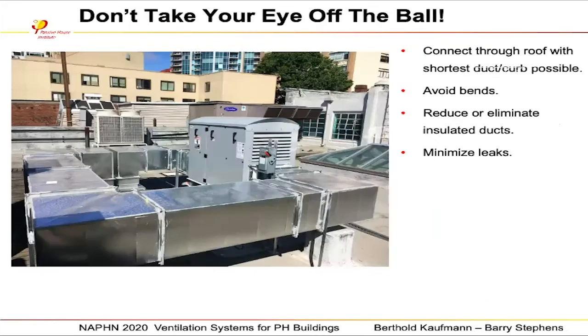One other thing with ductwork is beware the change order or the out of control contractor. What you can see here, the entry point for these two ducts through the roof is over here, excuse me, is here. And we've got all these 90 degrees, that's insulated duct, but the problem is you've got all those 90s that are going to cause a lot of static pressure. The other thing here is that the access for the filters is right here. You have to actually climb under the duct. So we see this on occasion where the contractor, without guidance, does these things.